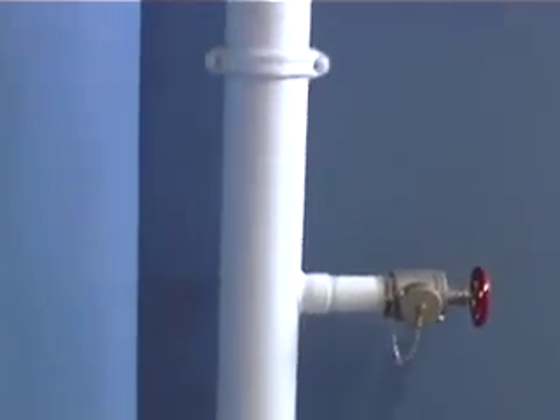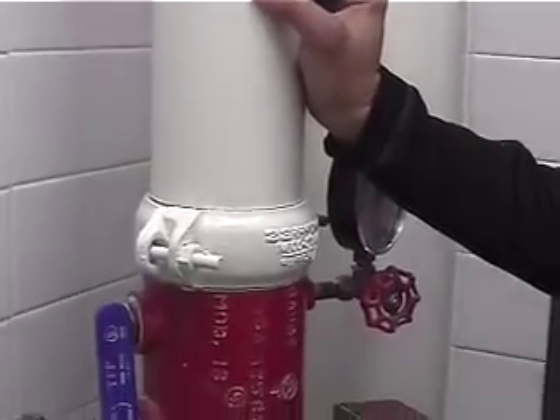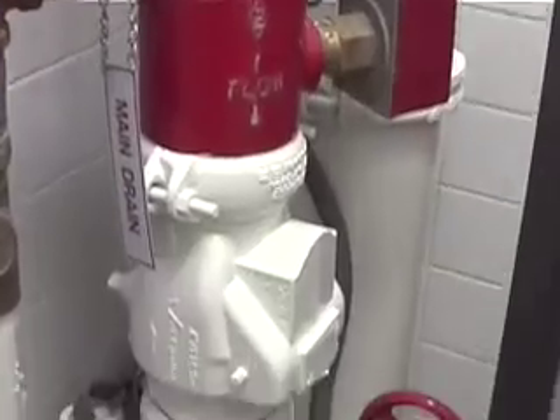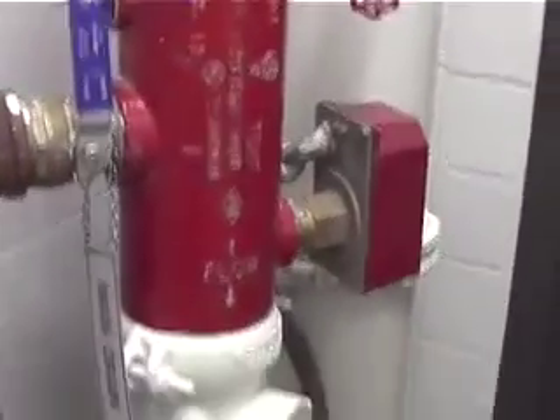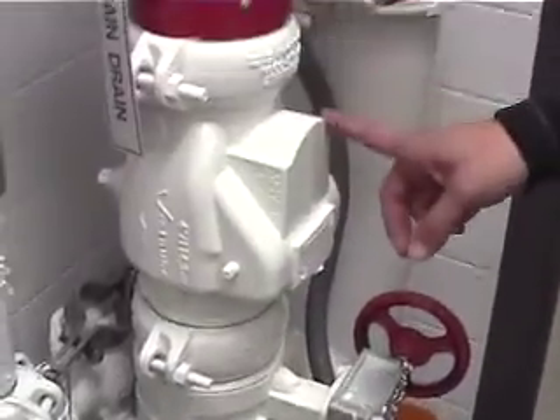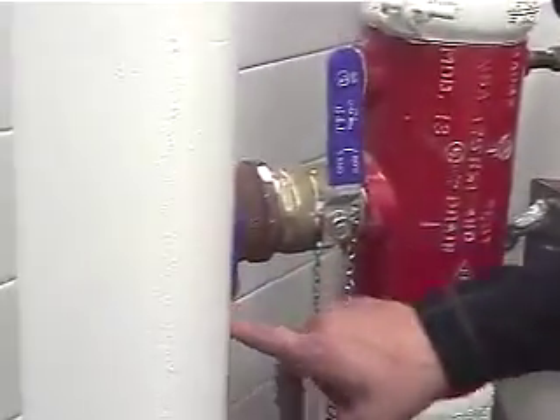This is stairwell S102, goes from floor 1 to floor 3. This standpipe with the hose valve on it, its control valve is above this access panel on first floor. This is the east wing, second floor, room 244. This is your second floor riser assembly, controls all 3 wings, including the middle area, except for the atrium zone. It's a typical assembly again. Got your control valve, check valve, your main drain, and your inspector's test.